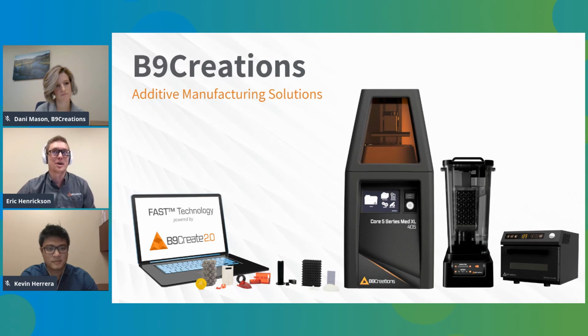Next up is our BioRes silicone material, which we also touched on a little bit earlier. Features of that material: it is an elastomeric material. It's got all the stretch and flex and stuff that you would be used to in a silicone type material. 70 Shore A hardness, and really quick recovery, which is something we don't see in a lot of materials. So if you bend it, it pops back to its original shape very quickly. Regulatory wise on that one as well, ISO 10993 is pending. We'll have that to offer you soon.